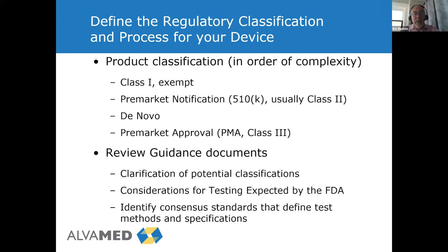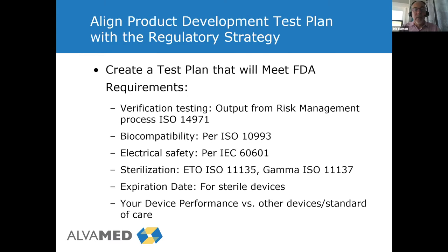So when I talk about review guidance documents, I'll talk about this in a bit. It gives you clarification on the potential classifications you would fit into, considerations for testing that the FDA might expect, and it also gives you the opportunity to identify consensus standards. You don't want to reinvent the wheel on how to test this. All the standards that the FDA accepts, all the ISO standards, all the IEC standards they accept, are listed in this database, and the link is at the end of my slides as well. So it's a really important process to understand what documents are out there and how to use them.